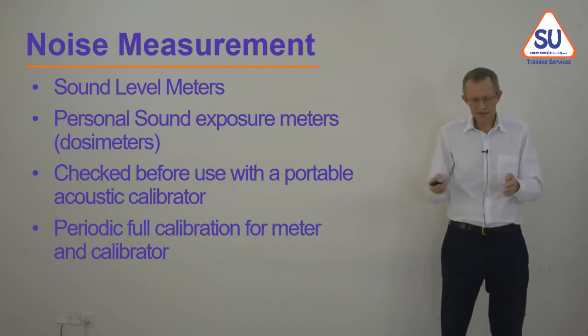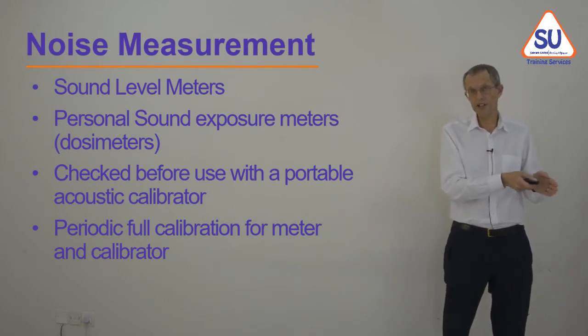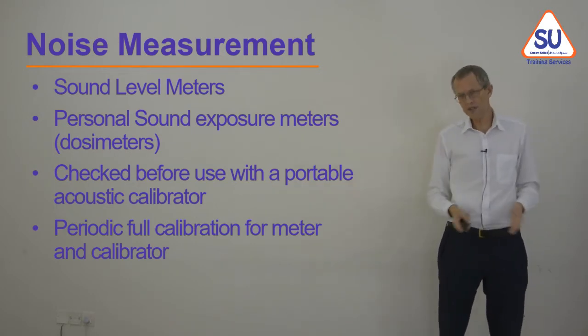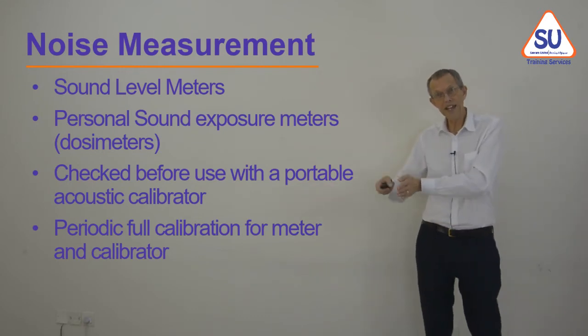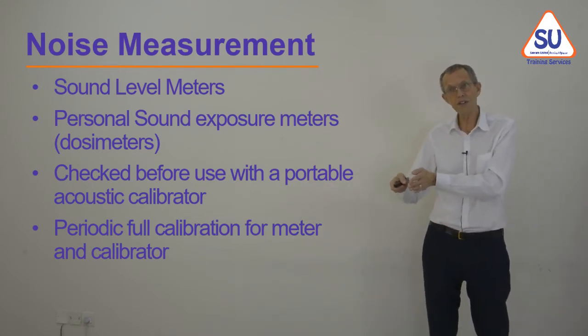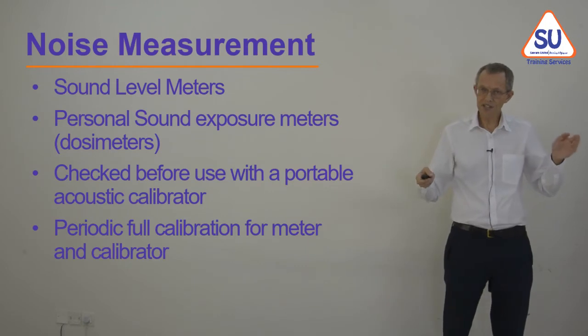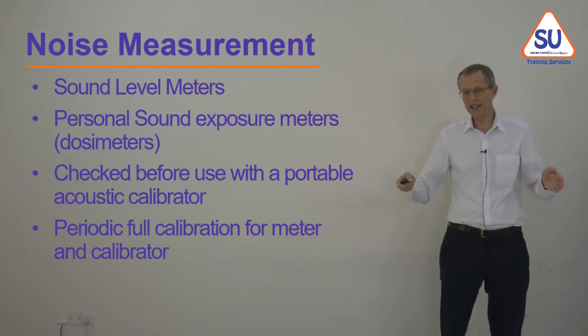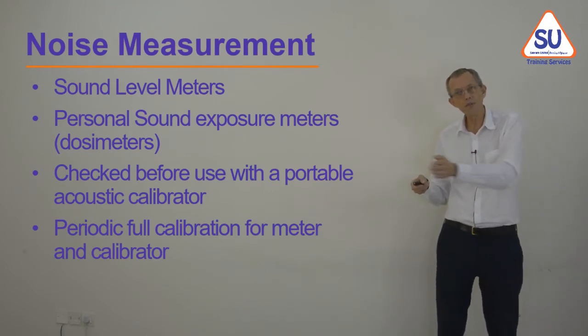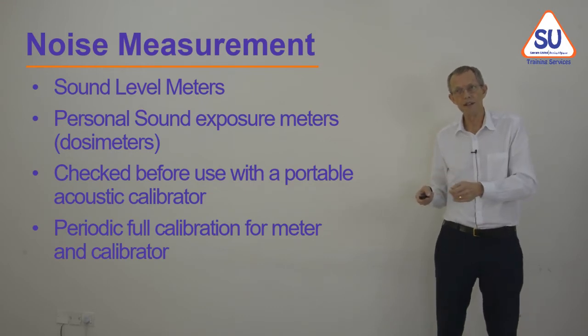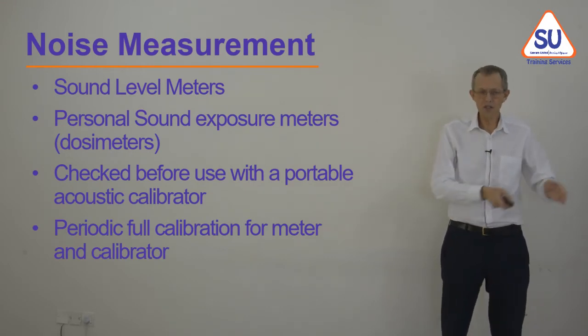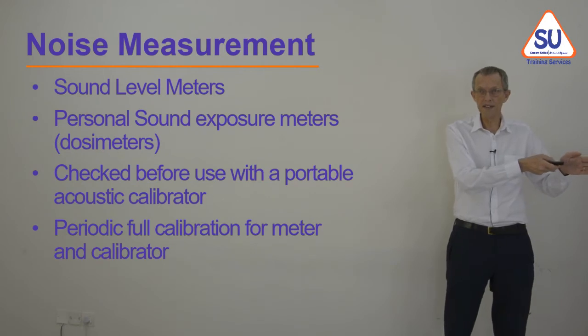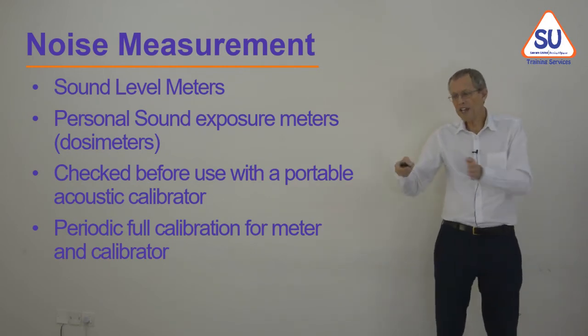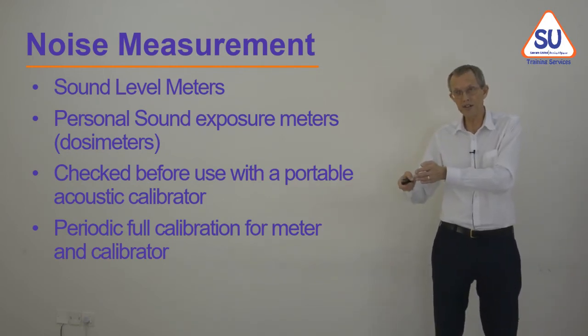Calibration means I've tested the meter, let's say at the beginning of a period of work, and it's giving the right reading. And then I do my measurements, and I test it at the end of the period, and it's still giving the right reading. If the test at the beginning and at the end are okay, then I can believe the numbers I got in between. They're accurate. But suppose the calibration shows it was good at the beginning, it was accurate at the beginning, but at the end of the period, it was not accurate.